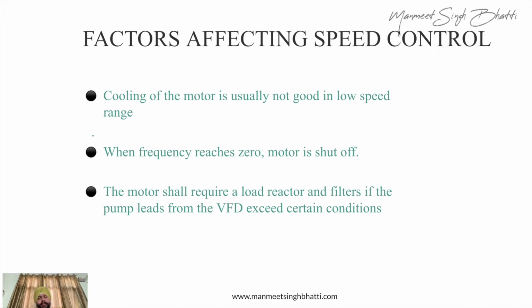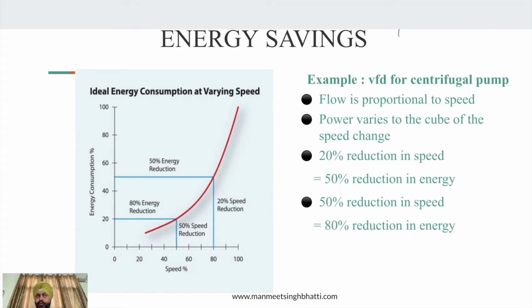This is basically because of the VFD output. If you see, the VFD output is a switching output. Now the switching output, if the distance is very short, is not going to make a difference on the motor. But if that switching output goes over a longer distance, you actually get a backlash also. Once the backlash comes, you have a very big challenge. The backlash is not affecting the motor, but it is affecting the drive circuit, because it's exactly the opposite of what is being generated by the drive. So it's some kind of short circuiting, but it normally happens with a longer cable, like when the cable is 500 or 600 meters from the VFD. So sometimes those kinds of challenges come up.